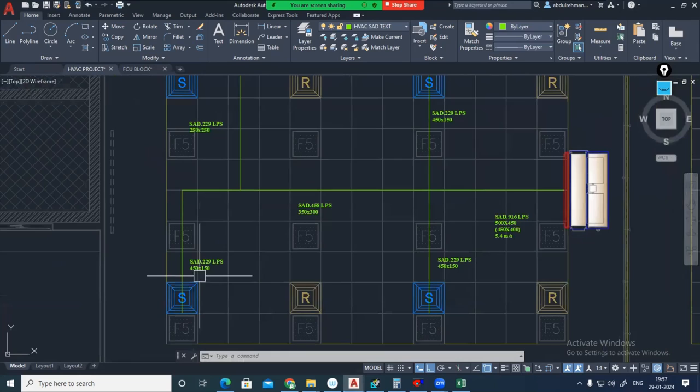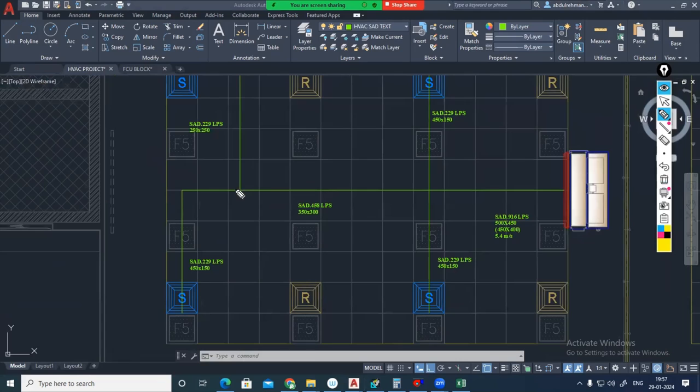Anyhow, now when we are connecting there, this duct will be coming like this. Then we can make an elbow there. Then we can connect. But if you want to connect an elbow like this, the width should be minimum how much? 450. Otherwise, like a reduced elbow, you have to use there. Because this branch has a width of 350 only, but here we need minimum 450. Elbow is not practically possible there. That's why I will be using shoe collar only. This one also means the same.